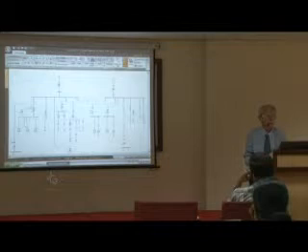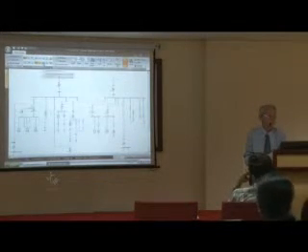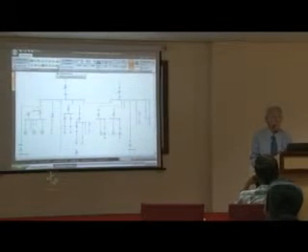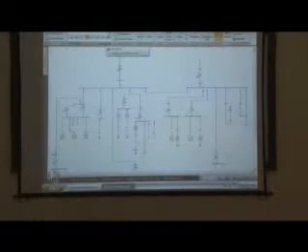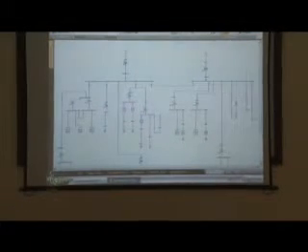Short circuit we looked at, and it'll give you whether you want the short circuit from phase A or phase B or phase C or three-phase or line to ground or line to line, or what's this one? Line to line, this is 2 lines to ground. So whichever analysis you want, they're there. Also, short circuit generates arc flash, and without getting into that, there are a couple of ways of getting injured electrically.